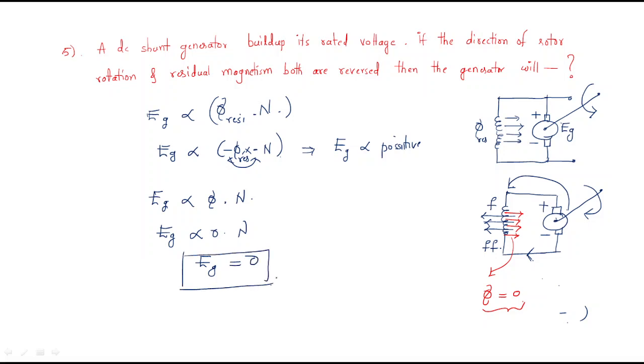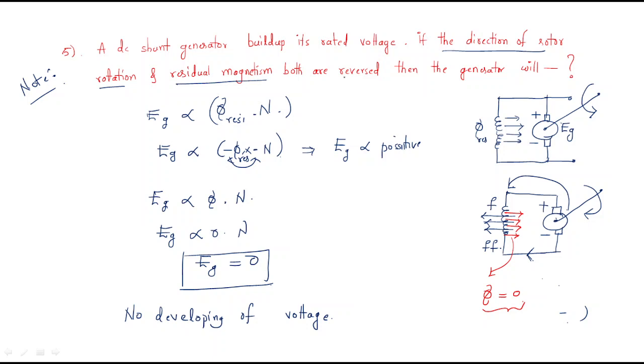At the initial stage the EMF is positive, but due to the positive EMF, the flux will change and become zero. Therefore there is no developing of voltage — that is the very important result. Note: if the direction of rotor rotation and residual magnetism are both reversed, the generator will not develop any voltage.